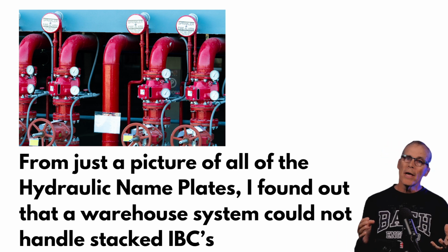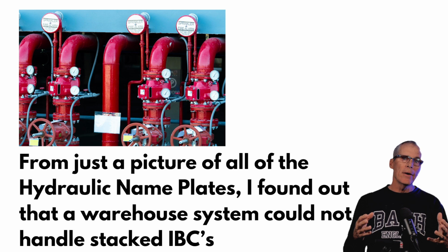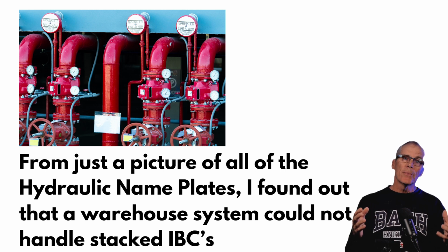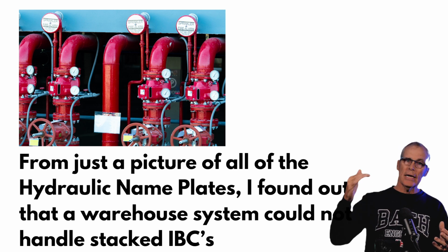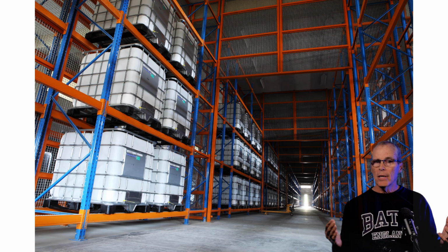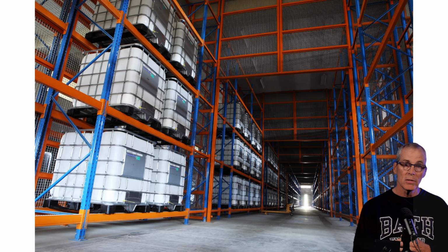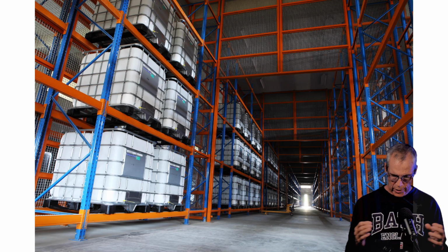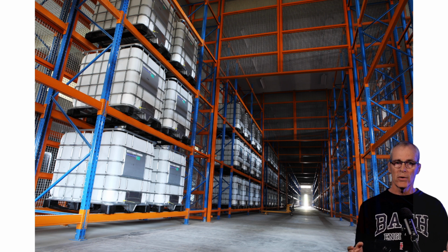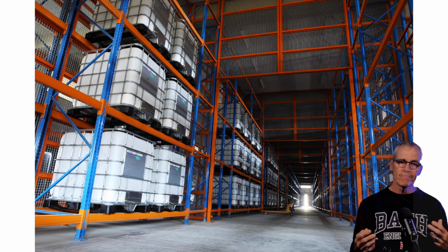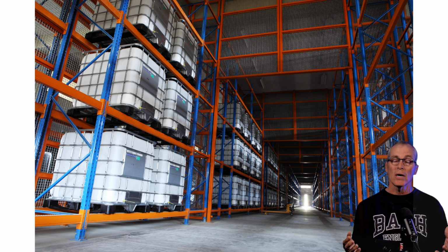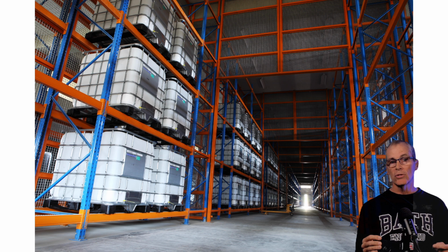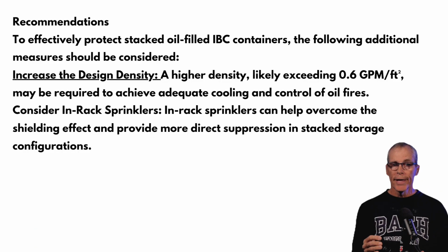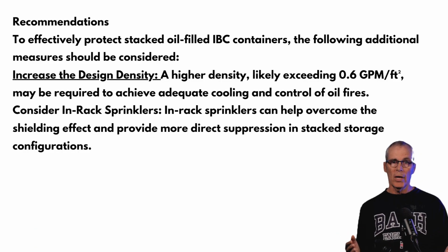I wanted to know, would this system I'm looking at be adequate to protect this warehouse if they had stacked IBCs? And it wasn't, okay? The response came back very thoroughly, explained what parts of the standards applied, what standards I could go to, to figure out whether this set of sprinkler systems was going to protect the hazards they were out there protecting. Well, they weren't, but I needed to know more.